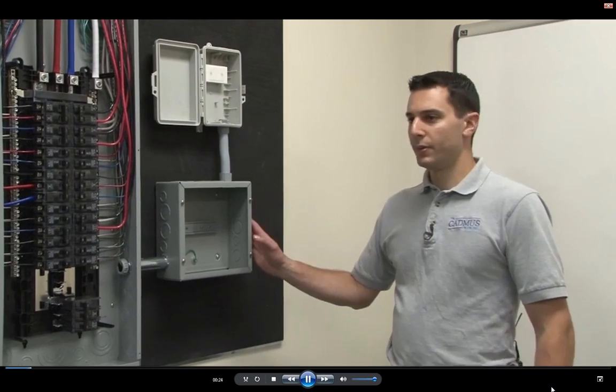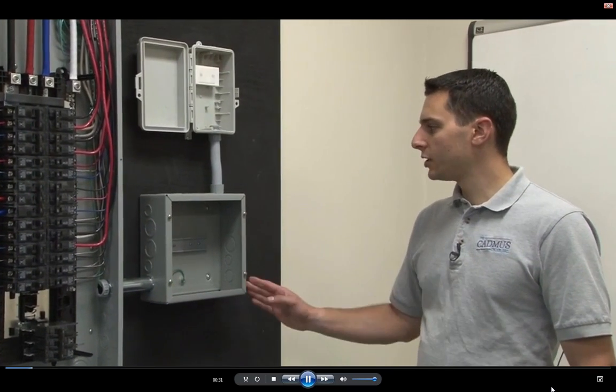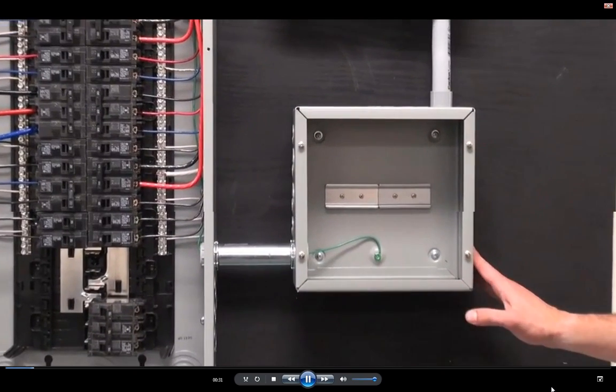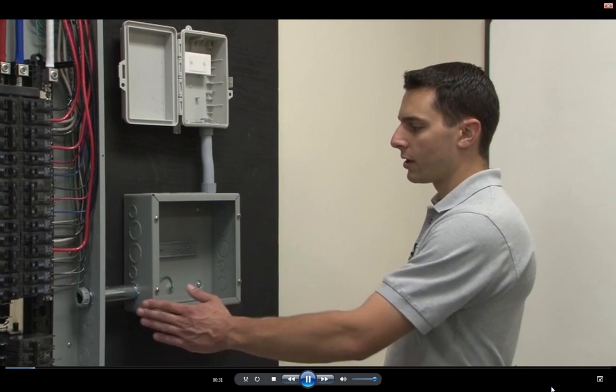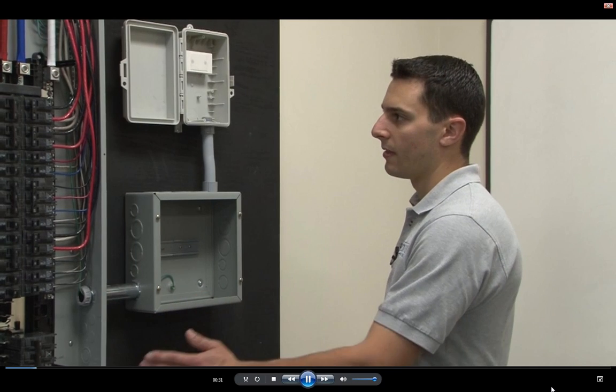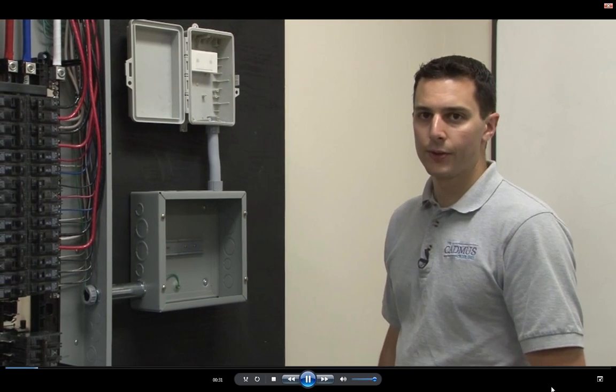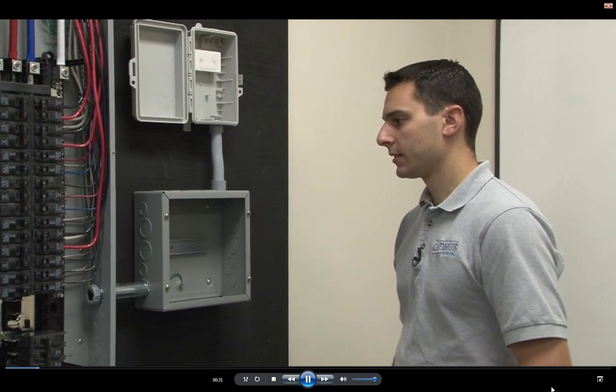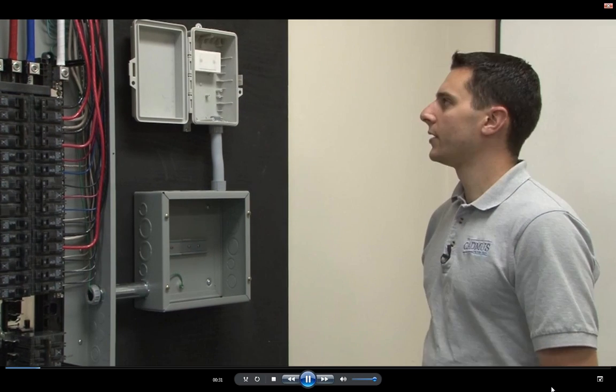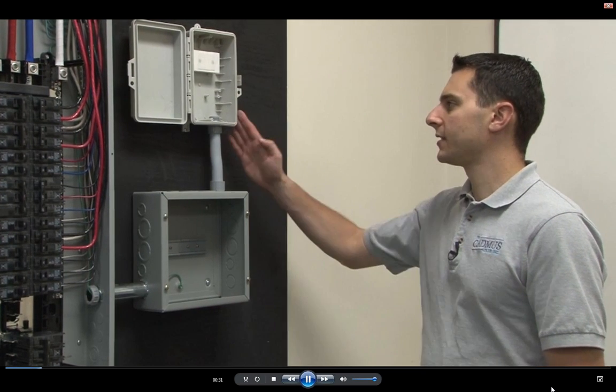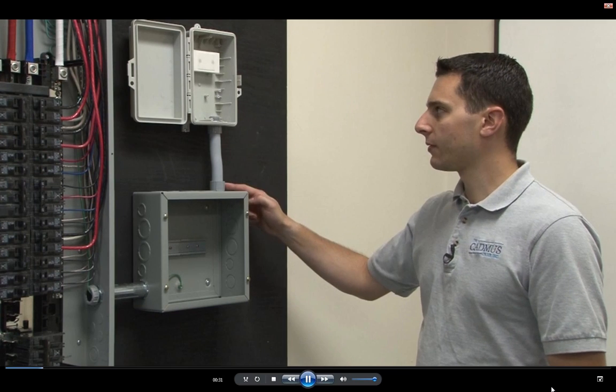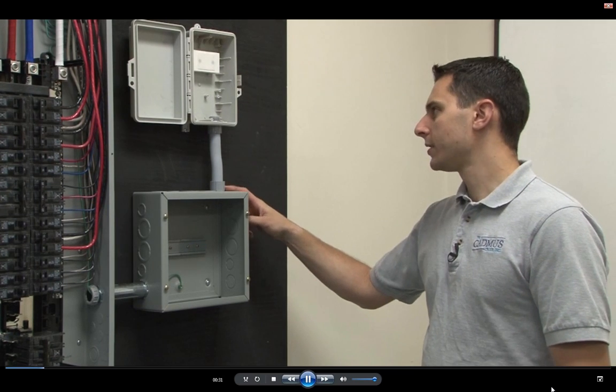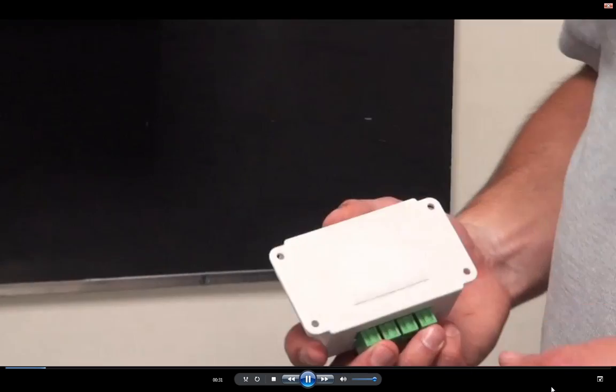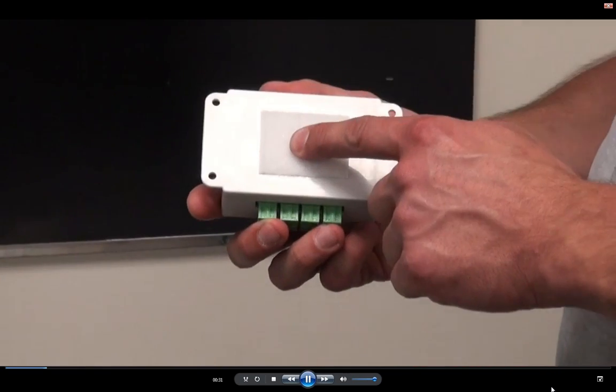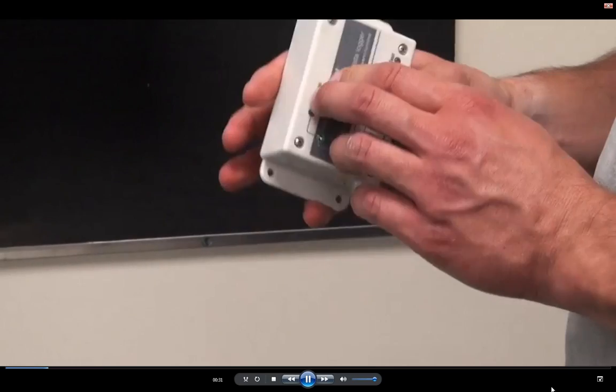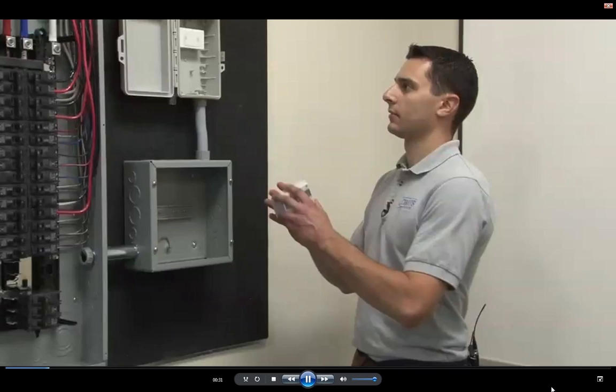For the E50B2, we'll install a standard 10-inch by 10-inch by 4-inch metal enclosure. We'll run a 1-inch conduit between the enclosure and the panel board for our 5 voltage leads and 6 CT conductors. For our UX120, we'll install a plastic enclosure with a plastic 3/4 inch conduit for our 6 communication conductors. For this installation, we'll use the Velcro mounting method in order to have ample space for our data connection.